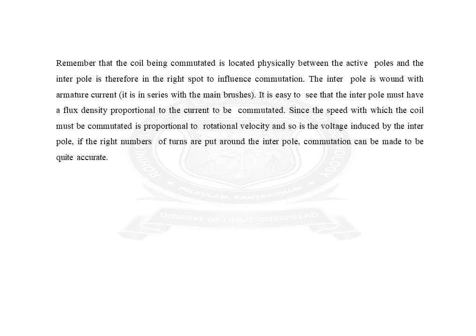The coil being commutated is located physically between the active poles and the interpoles, and the interpole is therefore in the right spot to influence commutation. The interpole is wound with armature current. The interpole must have a flux density proportional to the current to be commutated. Since the speed with which the coil must be commutated is proportional to the rotational velocity, if the right number of turns are put around the interpole, the commutation can be made quite accurate.